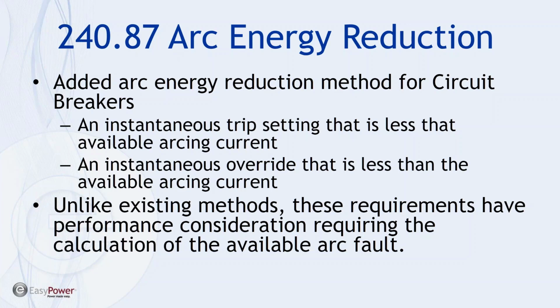So I'd like to emphasize that these changes are now in effect for the NEC with the release of the 2017 version. And the question is, does this make arc flash studies a requirement or more mandatory? And my point here is that the only way to ensure that this requirement is met is to calculate what the arcing current will be, and verify the device will function as needed at the place installed in the circuit. Again, that's part of equipment duty verification when you do a study.